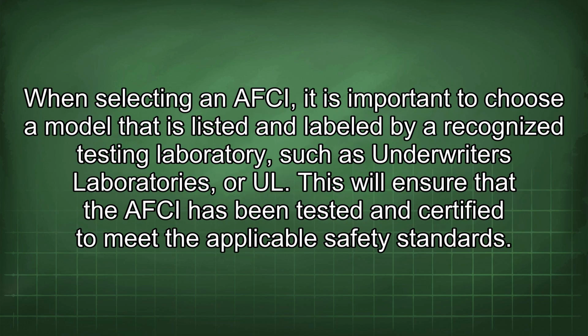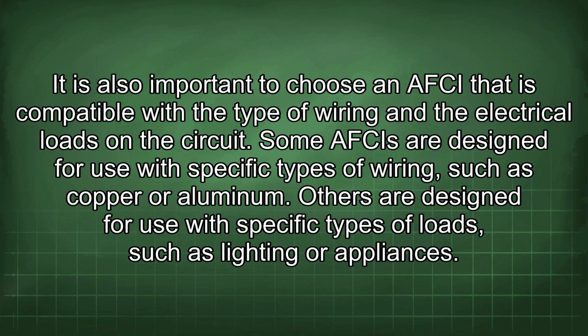When selecting an AFCI, it is important to choose a model that is listed and labeled by a recognized testing laboratory, such as Underwriters Laboratories or UL. This will ensure that the AFCI has been tested and certified to meet the applicable safety standards. It is also important to choose an AFCI that is compatible with the type of wiring and the electrical loads in the circuit. Some AFCIs are designed for use with specific types of wiring, such as copper or aluminum. Others are designed for use with specific types of loads, such as lighting or appliances.